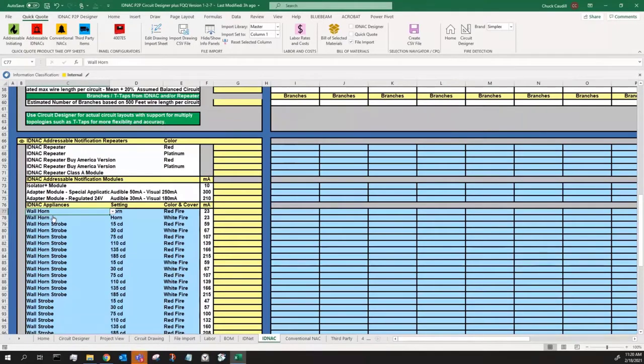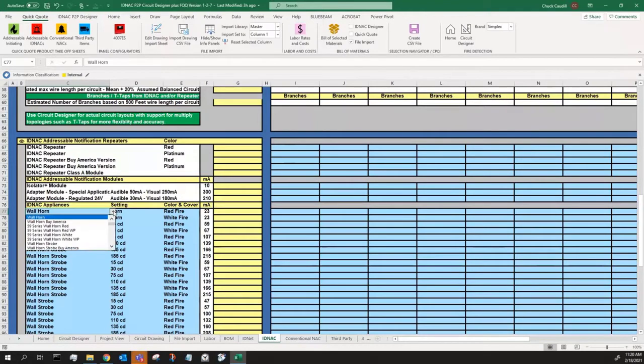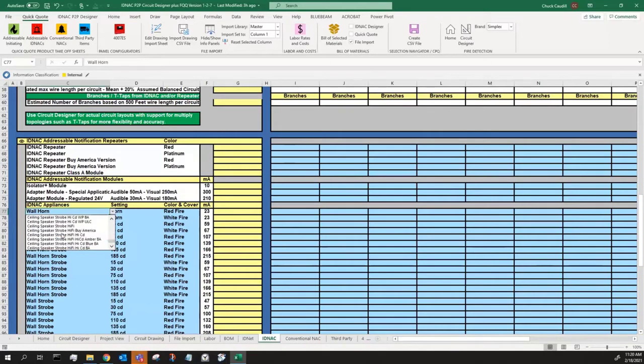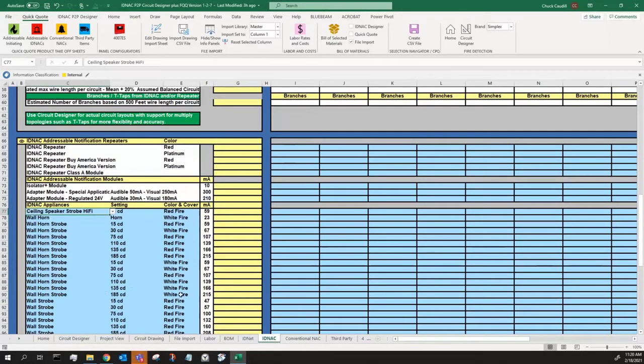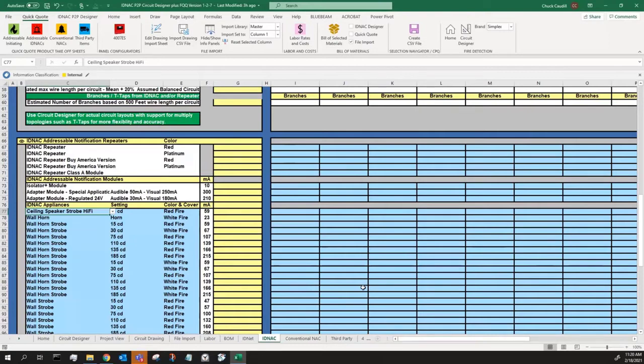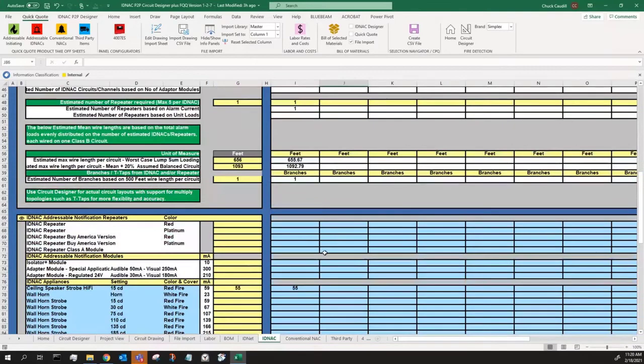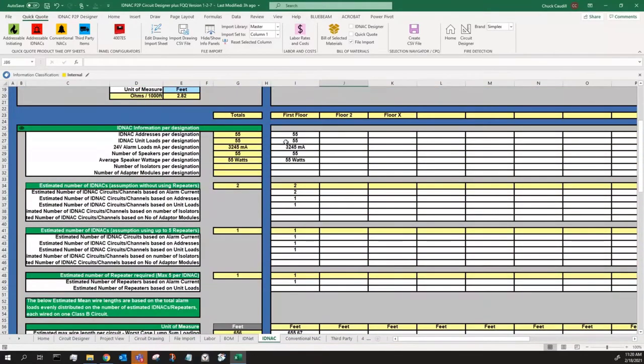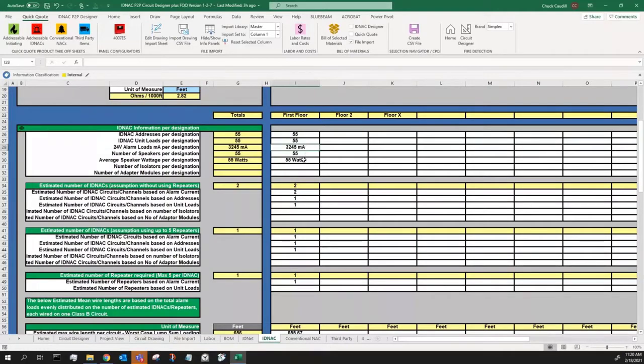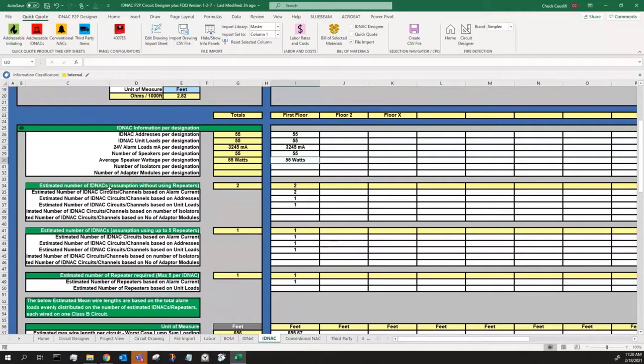When you get to the notification IDNAC, you might be doing a voice system that has all speakers on it. So you don't need any horn strobes or vice versa. You can set this sheet up to your liking, to your parameters. You can say I'm a contractor that does mostly voice systems and I can put speakers as my options here. You can save this sheet as your template and you might have two sheets. You might have a voice evac template and a non-voice template. So it opens up and your items are at the top. As you choose these items, if I put in 55 of these speakers, up top it gives me the quantity. I have 55 speakers, 55 unit loads. There's my amps required for the strobes and there's my wattage requirement. Down in these boxes, we give you some more information. How many IDNACs did I need without using repeaters? It would be two. If I'm going to use with repeaters, I can say I need one IDNAC and I need one repeater.